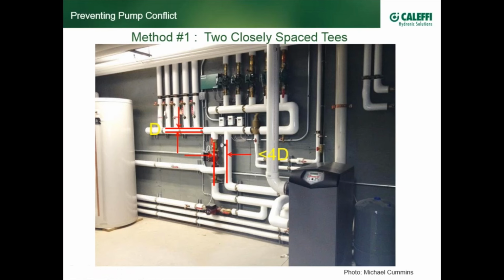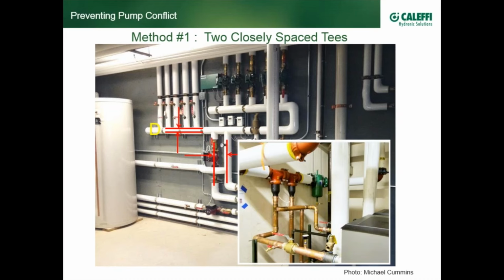If they're ECM pumps, it's going to cause them just to work a little harder to maintain delta P or delta T, however they're being controlled. And if they're fixed speed or single speed, it would reduce the flow rate and they would be fighting one another. And that's what you want to prevent, thus the popularity of hydraulic separation. Now, that's one method, closely spaced T's. Recall this photograph from earlier. Here's your closely spaced T's.